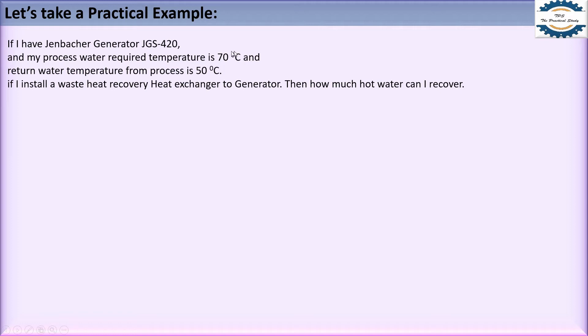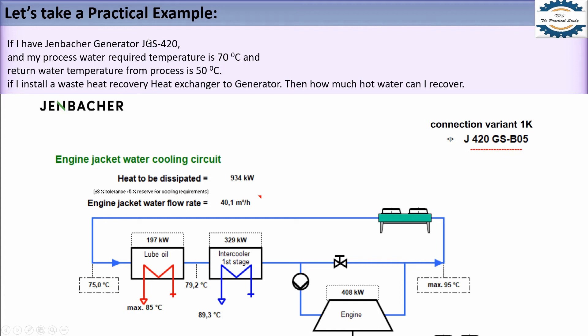We have two temperatures given on the secondary side, and the secondary flow rate is what we need to calculate. For the primary side we have no data, so we will take the technical data sheet of the Jenbacher JGS420. From that data sheet: the hot water flow rate on the primary side is 40.1 m³/hr, the water returning to the generator is 75°C, and the hot water coming out of the generator is 95°C.